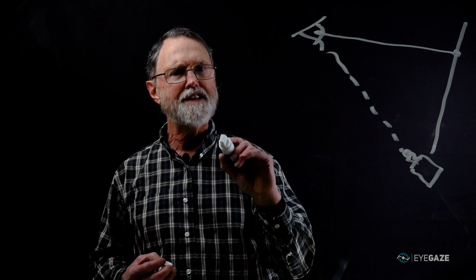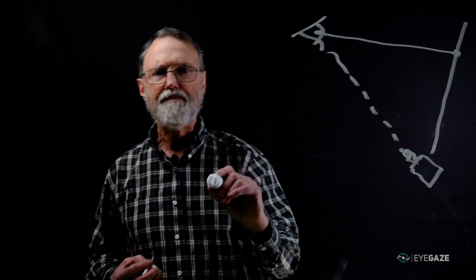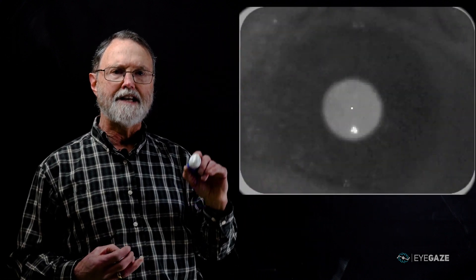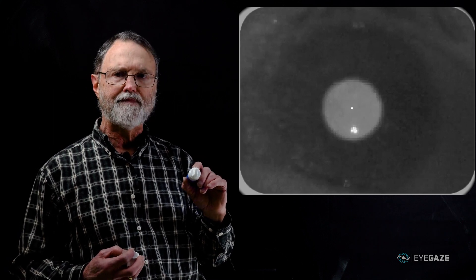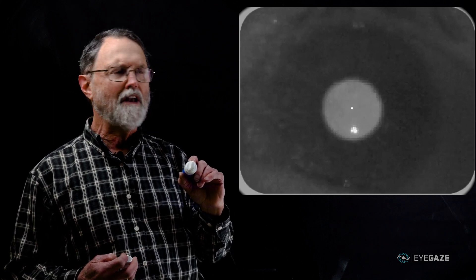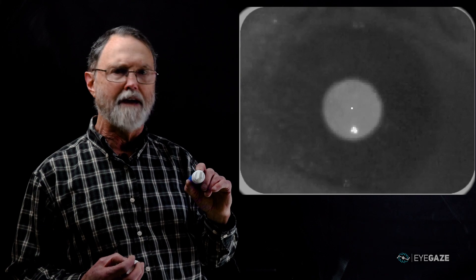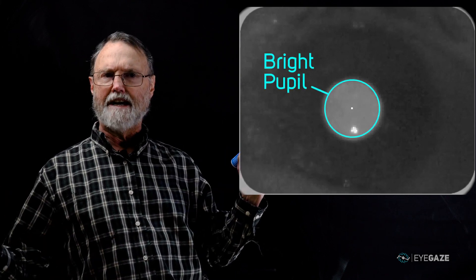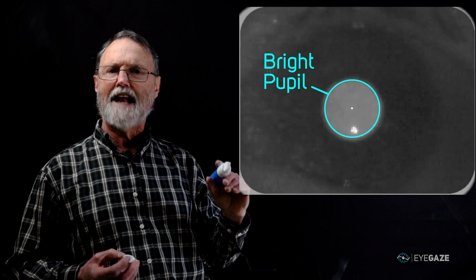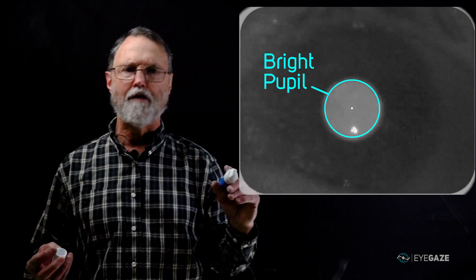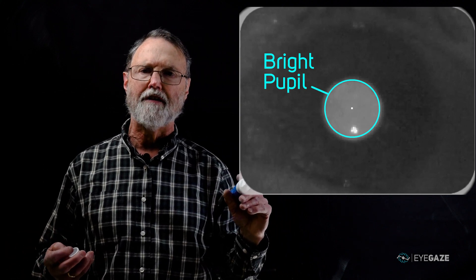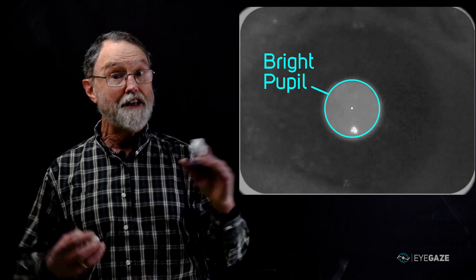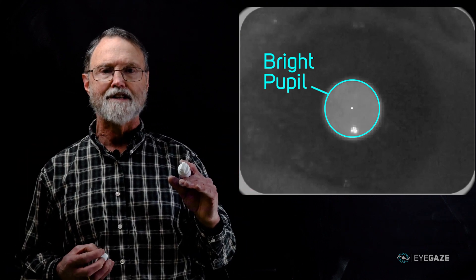So what does the camera see? Here's a picture of an eye as seen by our camera. Note that there are several interesting features of the eye image. First, the pupil looks bright — it's not the black pupil that you and I normally see when we look at each other. This is called the bright pupil effect, which is the deer-in-the-headlights look.